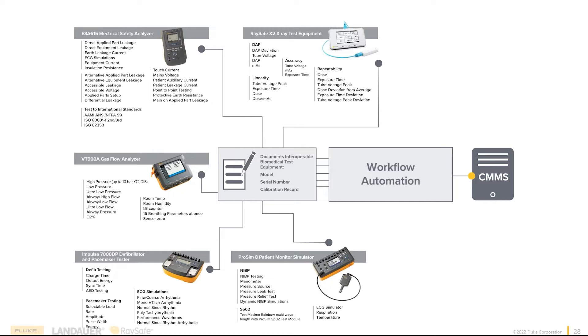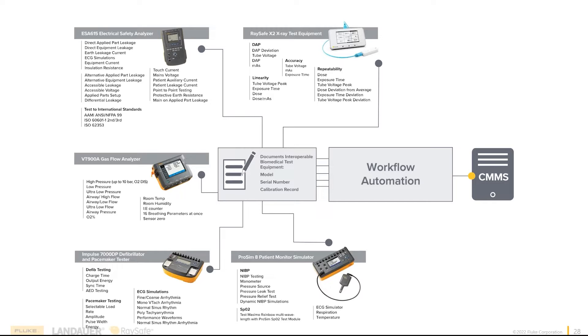Or maybe you had a failure where your meter got knocked out of calibration. Well, now you need to go back for three or four months and make sure all those procedures were done correctly and had the right results. Now you can go back in and pull all that and find each and every one. If you get into the OEM field, we record this a lot on our work orders. This is going to do it for you automatically.